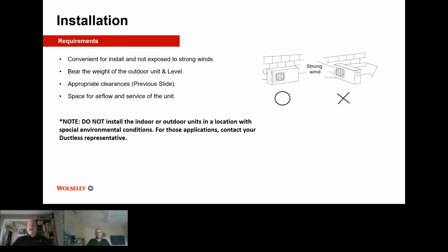So, number one here, convenient for installs and not exposed to strong winds. The reason why strong winds are a factor in determining our outside potential spots for location is that a strong wind could prevent the heat exchange during defrost cycles, or when you have a heating or cooling cycle. And what I mean by that is, let's say that you put this on a north side or a west facing wall where the prevailing winds usually come up. That's what they are in Alberta here.